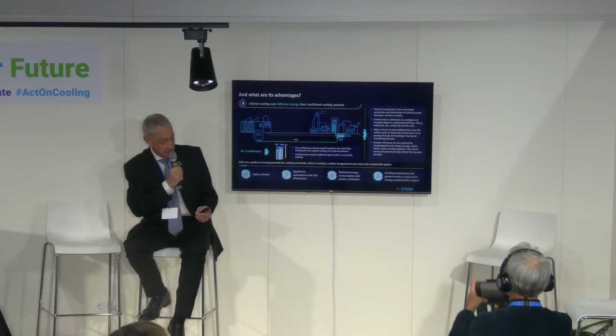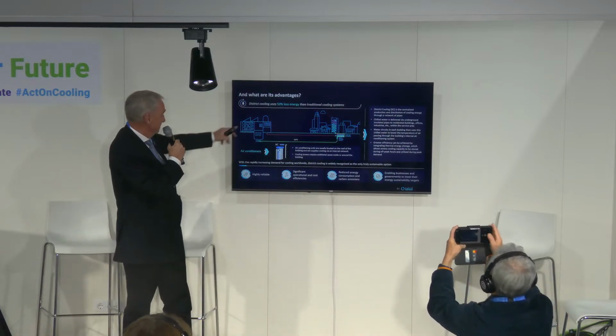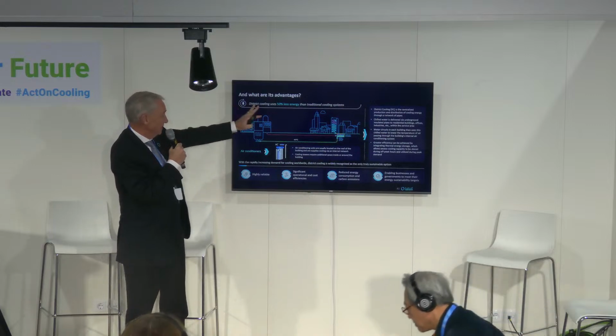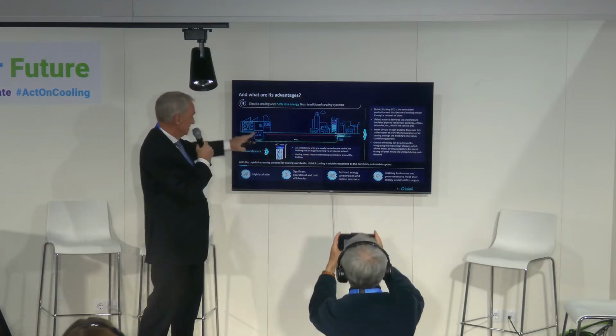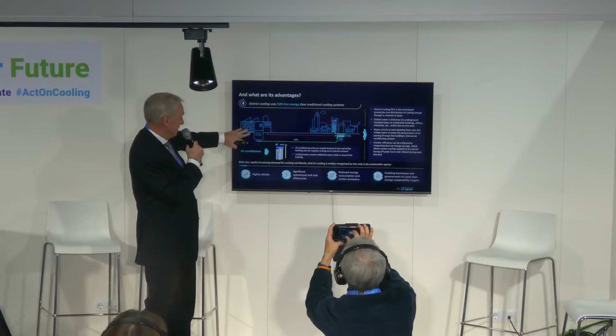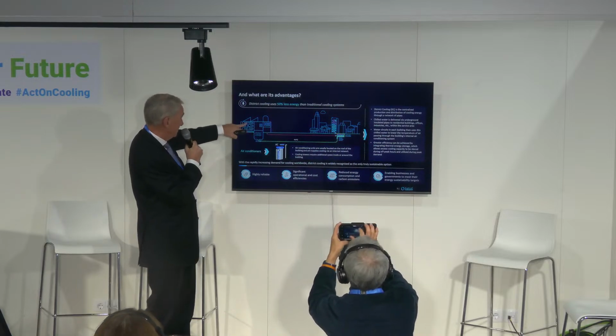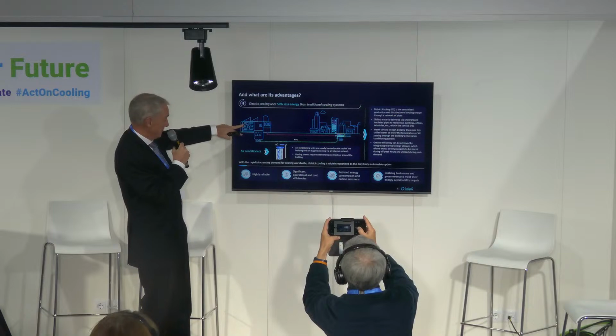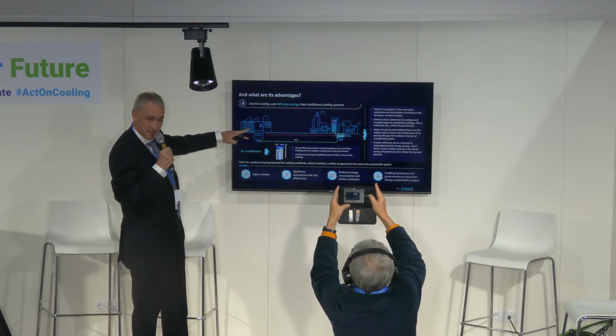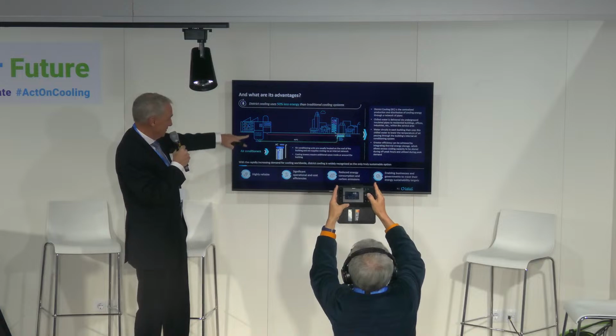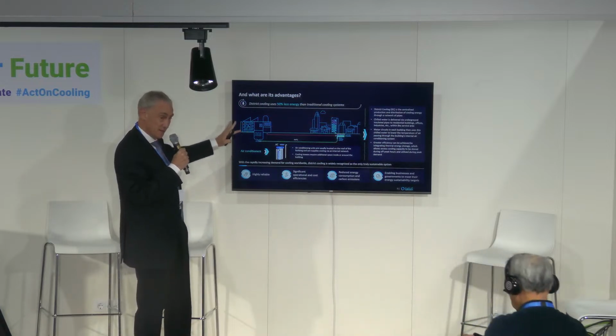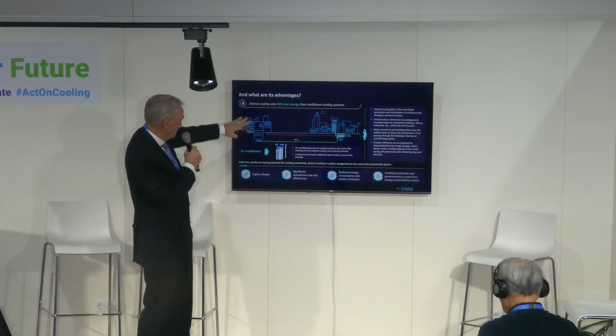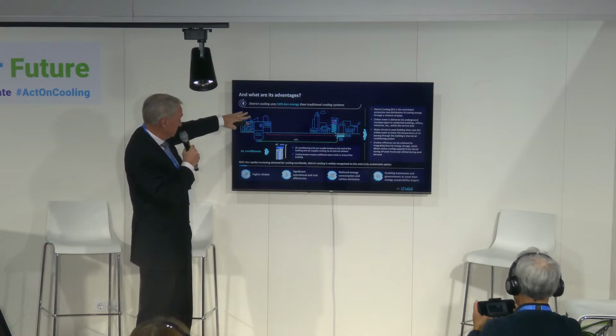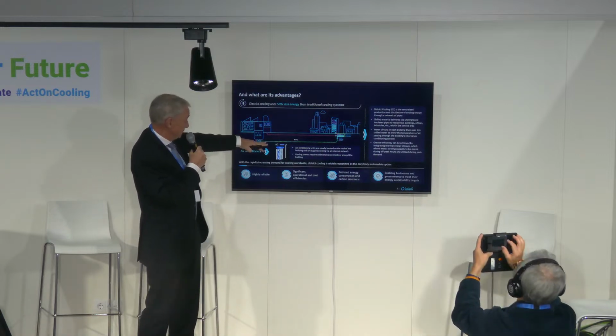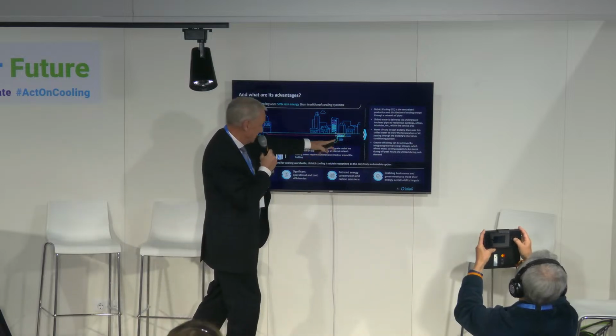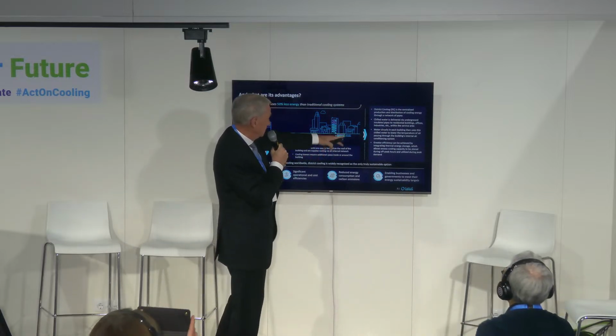So this is a diagram that just shows quickly the flow of district cooling around the district. Here we have a plant. We supply cold water, using a big refrigeration unit, chillers. We had a very good interaction yesterday with people from Trane who were talking about their chillers, and we use a lot of Trane chillers. We use other makes too, but Trane and others make chillers that cool water down to 4.4 degrees, and send it through an underground network into an energy transfer station.